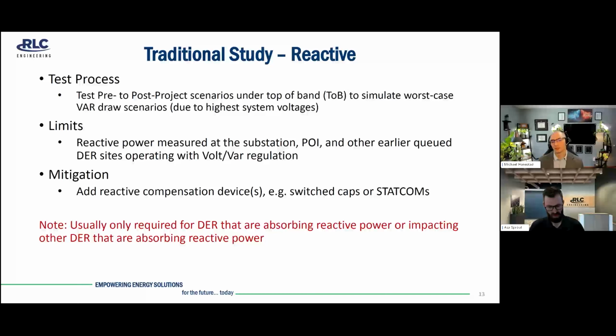So you'd look at reactive power measured at the substation POI and potentially other previously queued DER sites, and you would size your reactive compensation accordingly. The reason why you're looking at other previously queued DER sites is you need to make sure that the DER that is being added to the system is not increasing the burden on those previous sites. It's entirely possible that you had previous sites operating in volt VAR. You go to study this one at Unity, it passes all of your voltage checks. However, it's actually increased the burden on those previous projects. It's the previous projects that picked up the regulation and voltage suppression of that new project. So by looking and ensuring that those other previously queued projects have not increased their VAR burden, you're ensuring that the new project is essentially picking up its own share of mitigating the voltage rise.